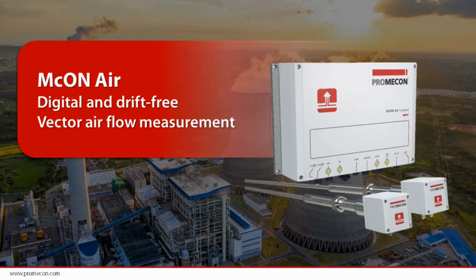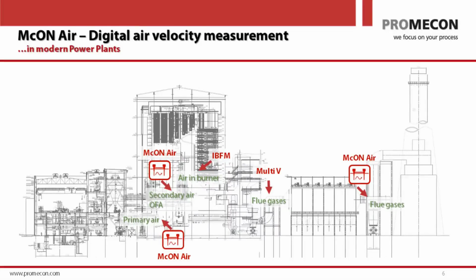First of all, let's have a brief look at where you can measure in your plant in order to optimize your boiler. Every boiler, of course, has an air intake, and the air intake, or fresh air intake, is used to route the air after it's preheated to the mills as primary air, or to the burners as combustion air or secondary air, including the overfire air, the OFA. What else can you measure? Of course, in the boiler, you also find gas flows after combustion. These would be flue gas flows out of the air heater, flue gas flows into the precipitator, or out of the precipitator into the ID fan, or into the scrubber units.